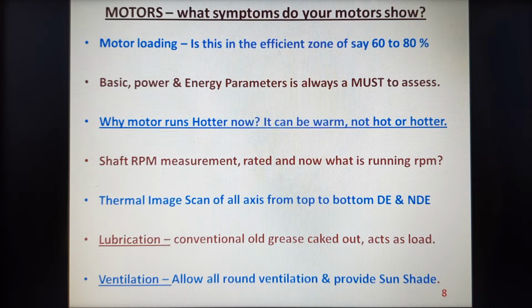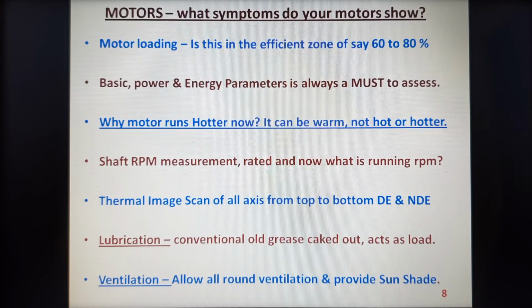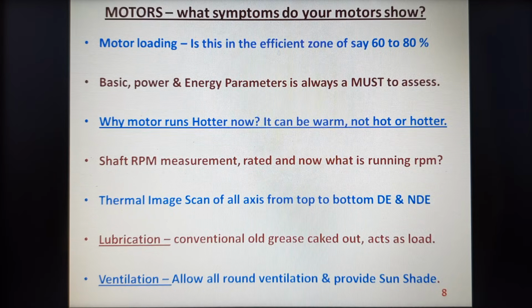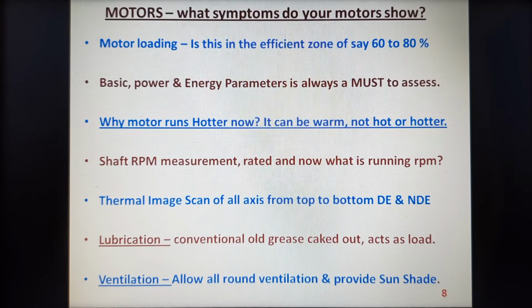So let us try to monitor the shaft RPM of the motor for the given 50 hertz given by the EB supply. What is the motor deliverable RPM, either 1450 or 1470 or 1480, matching the given load? What is the motor RPM and the load RPM? This will give an idea of what is the slip that is happening in our motors. For the thermal image, you can use either a thermal gun or a basic thermal imager. I will discuss that in length later as such.